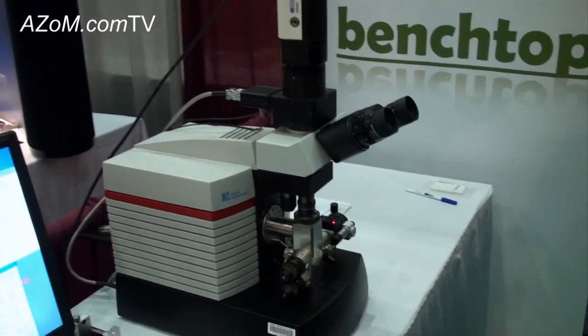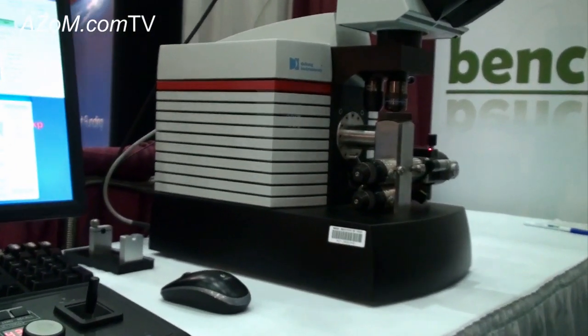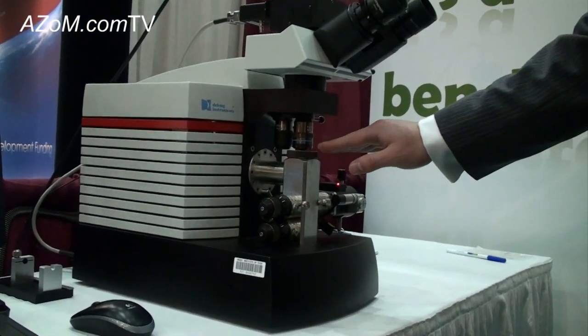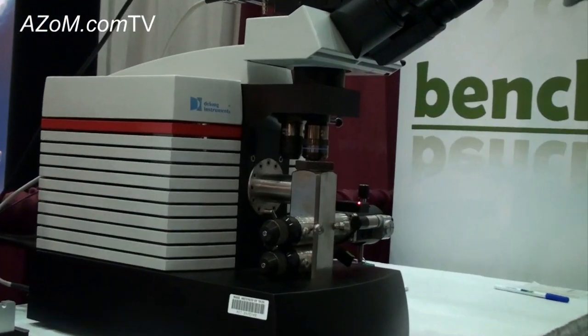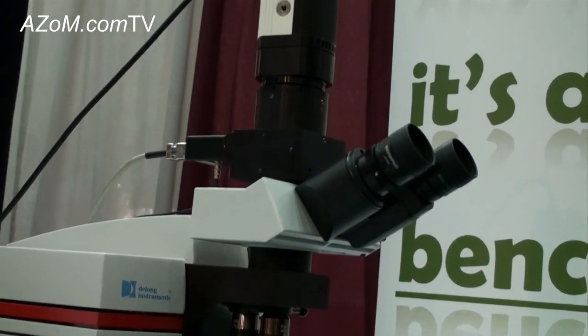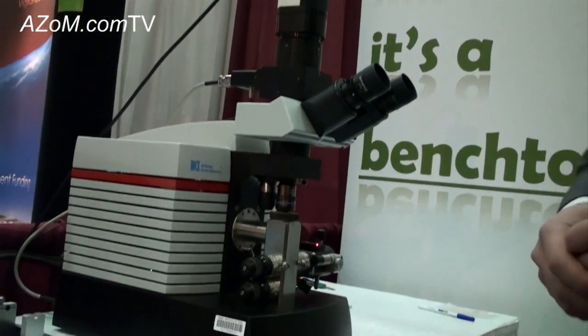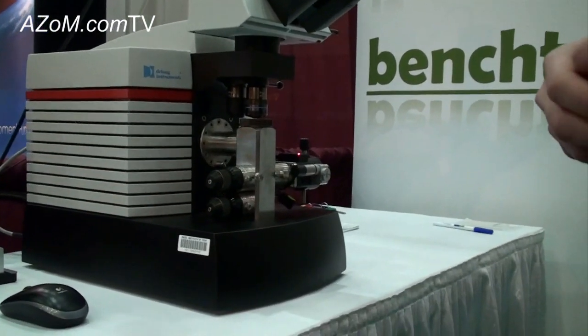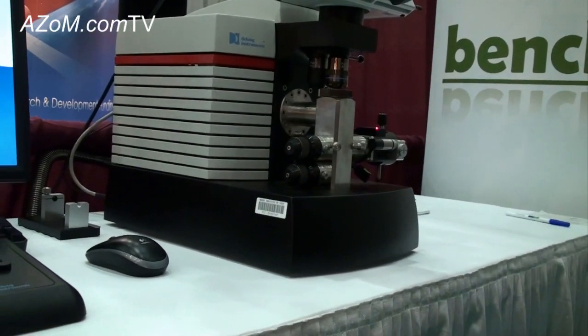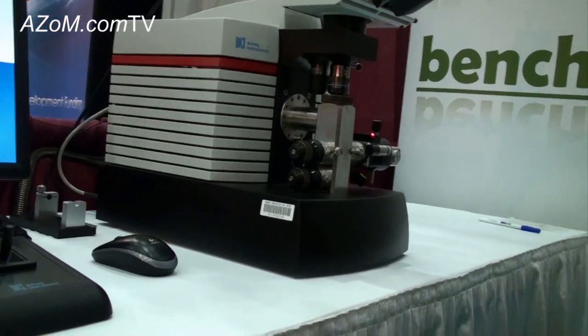In terms of resolution, it's capable of 2nm resolution in TEM mode and 3nm resolution in SEM mode. The entire electron microscope is essentially this portion here. We have our phosphorous screen at the top of the column, and essentially an optical microscope going up to our CCD detector for TEM acquisition. We have a photomultiplier for STEM and two backscatter electron detectors in the column for SEM detection.